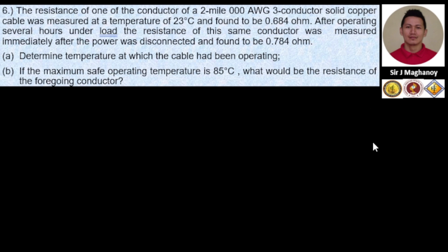Let's check the given parameters. We have the initial temperature, and the initial resistance R1 is 0.684 ohms. Since the resistance was measured again immediately after disconnecting, R2 (our final resistance) is 0.784 ohms. The initial temperature is 23 degrees Celsius. The temperature coefficient is not directly mentioned, but since it's a copper cable measured at 23 degrees Celsius, we can determine our temperature coefficient.